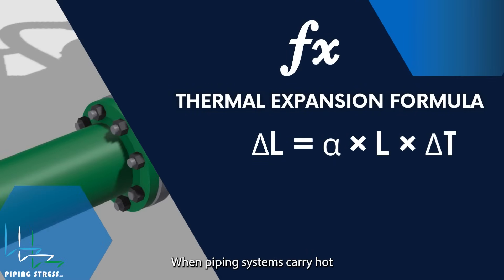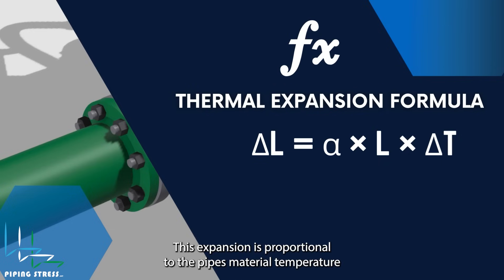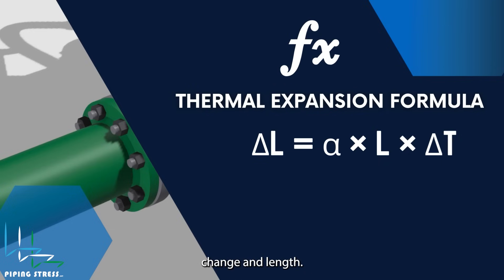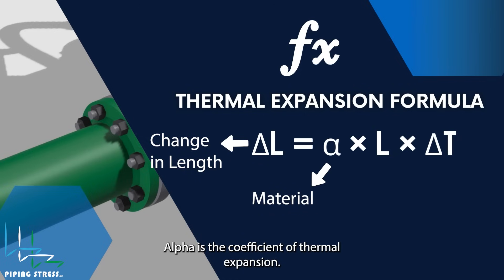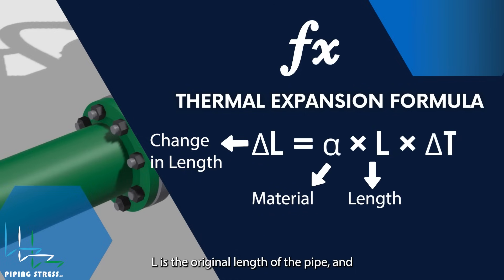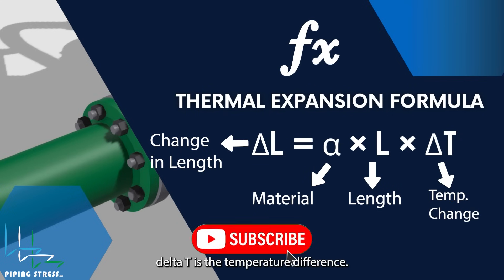When piping systems carry hot fluids, the pipes absorb heat and expand. This expansion is proportional to the pipe's material, temperature change, and length. The formula for thermal expansion is simple: Delta L is the change in length, alpha is the coefficient of thermal expansion, L is the original length of the pipe, and delta T is the temperature difference.